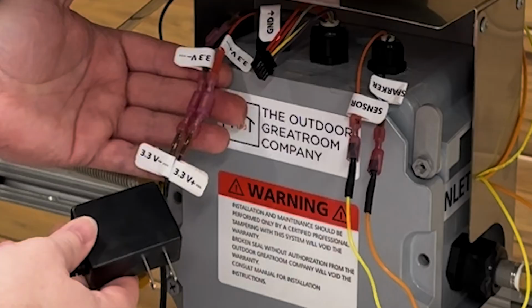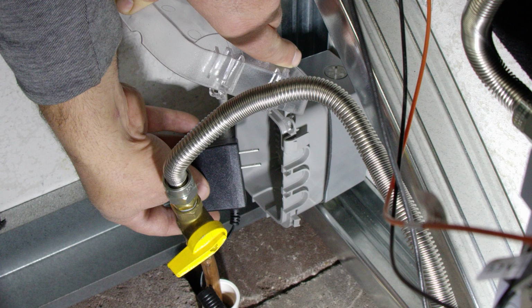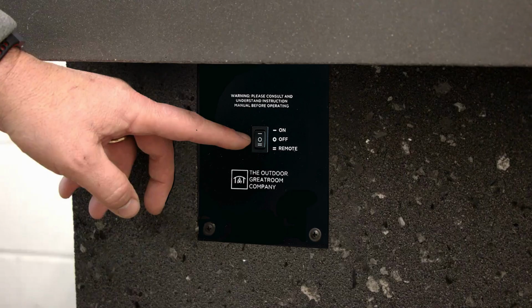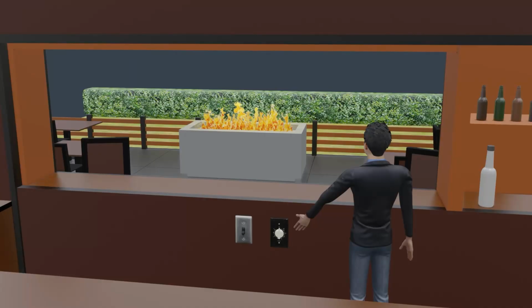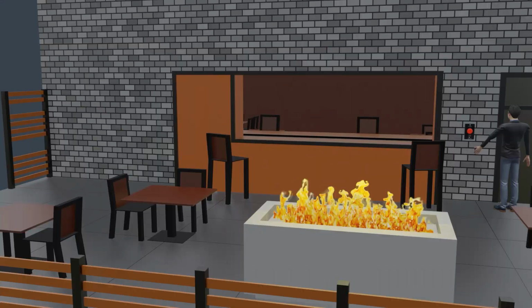Connect the positive and negative wires to the transformer wires. It is important that the positive goes to positive and the negative goes to negative. Before plugging in your transformer, it's important to know that if you have power to the junction box and if your switch is in the on position or you have the bypass switch installed, the flame will turn on. Best to make sure the switch is in the off position and your power is shut off to the junction box before this step. If you are using controls away from the appliance, your electrician should have wired a switch or timer on the electrical circuit and, if applicable, installed the e-stop on the same circuit.